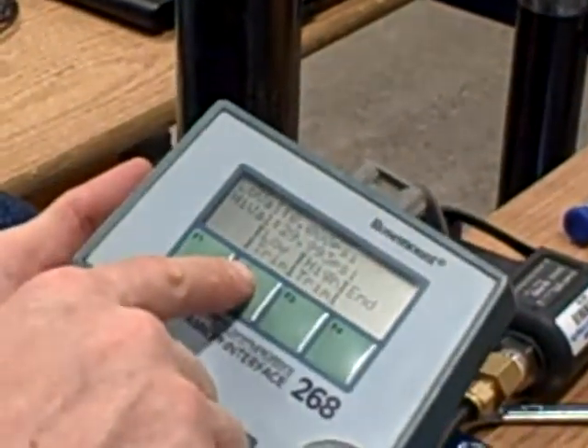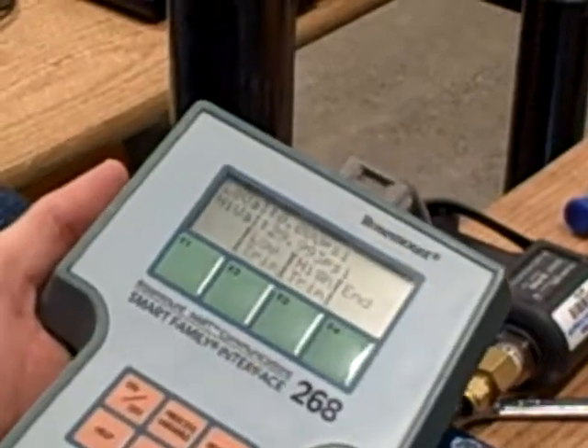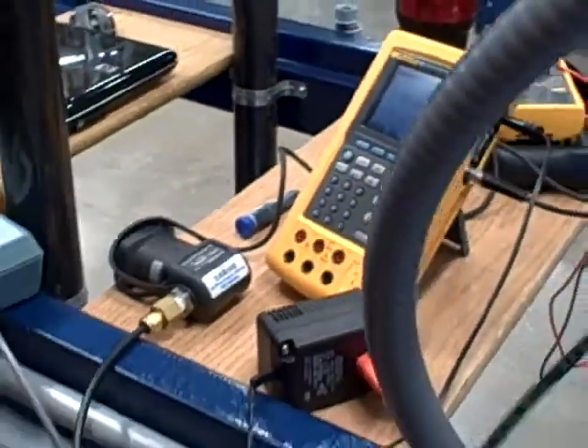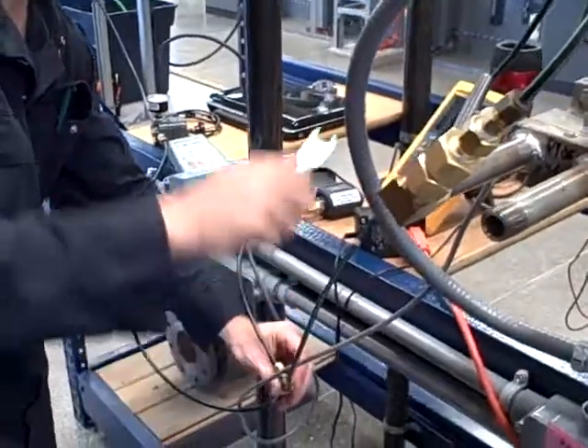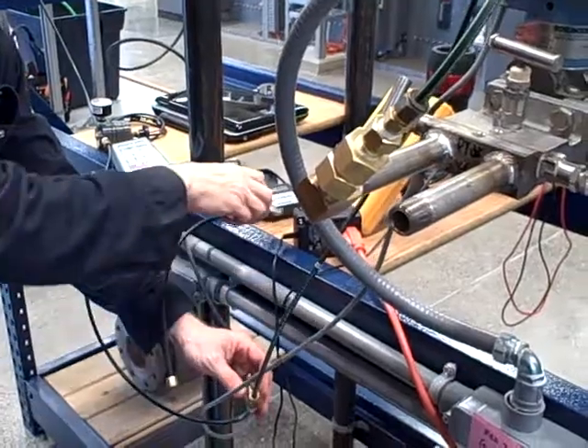Now it says low trim. Let's go ahead and do a low trim. So shut off the air pressure. What I will do is set this to the side. I will bleed off all the pressure by undoing one of the tube connections. We could have also moved our manifold and vented through the manifold.